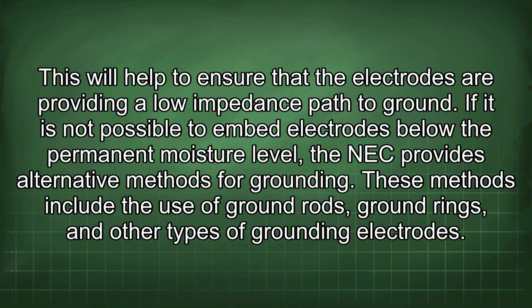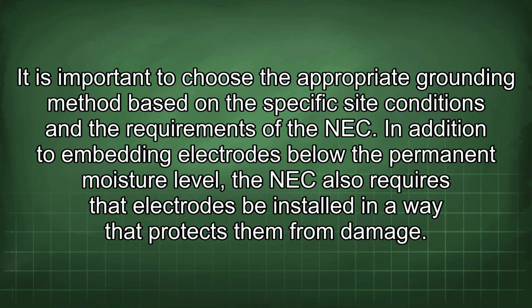This will help to ensure that the electrodes are providing a low impedance path to ground. If it is not possible to embed electrodes below the permanent moisture level, the NEC provides alternative methods for grounding. These methods include the use of ground rods, ground rings, and other types of grounding electrodes. It is important to choose the appropriate grounding method based on the specific site conditions and the requirements of the NEC. In addition to embedding electrodes below the permanent moisture level, the NEC also requires that electrodes be installed in a way that protects them from damage.